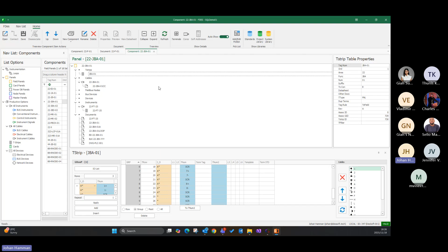Now the documents again will be my termination drawing for this JB. So if I preview this, I get this drawing without again having to draw any lines. So there's my junction box, there's my 24 terminals, and there's the tag from the P&ID on this first instrument and all the instruments that are connected to this JB. There's the 8-pair cable connected to the PLC, the landing strip, as we have seen on the loop drawing.